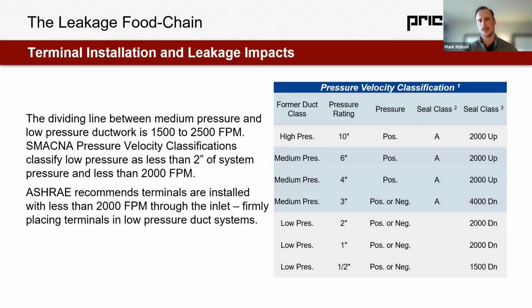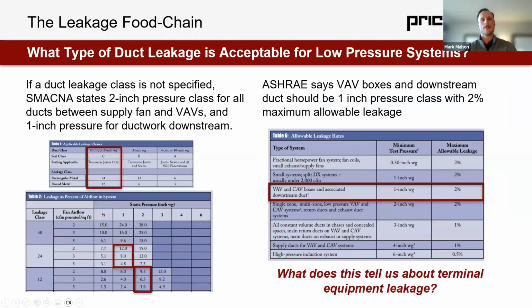The terminal is too close to occupants, too close to the zone. We don't want to make it loud. And the byproduct of that is the inlet is the smallest cross-sectional area of the terminal. The ductwork downstream is going to be larger. Therefore, we're firmly putting terminals always in low pressure duct systems. They're always plugging into low pressure duct systems in really every installation, vertical market, doesn't matter the application. Terminals are almost always low pressure duct systems. And so that kind of moves us to the SMACNA discussion and the ASHRAE discussion of if it's a low pressure system, what kind of duct leakage is acceptable?